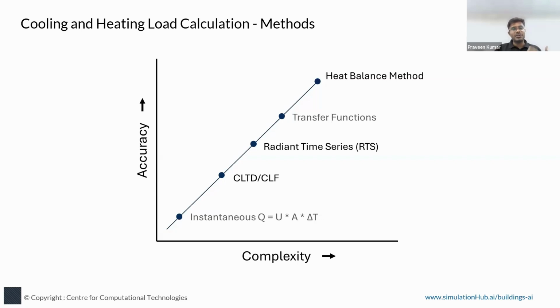Then got introduced the CLTD, cooling load temperature difference, and CLF methods. This is approximated or based on experiments, populating the data for time lag. So instead of delta T, you substitute CLTD from those data tables. Again, this has certain compromises on accuracy. These two methods we can do with the help of Excel sheets probably.